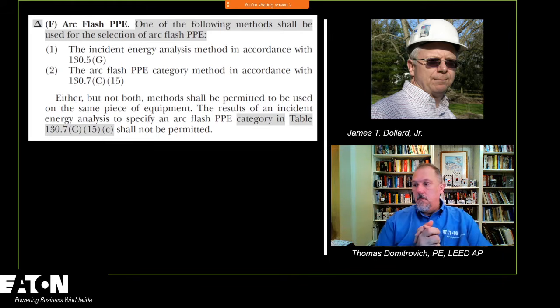At the time, it was a controversial way to go. It was direly needed in the industry because we had nothing. And when you take a look at it now, the individuals that put that together almost look like geniuses. It works. But here is one of the big problems with taking the results of an incident energy analysis and trying to tie it in to the arc flash PPE category method.